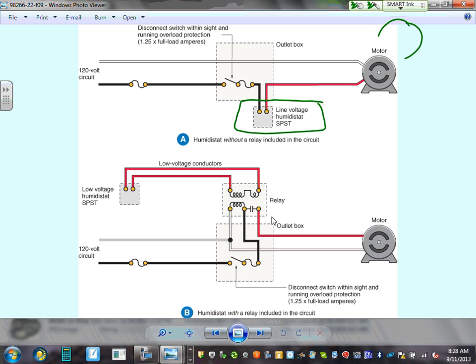You can buy a device like this, where you bring the hot in and the hot out, made to be a humidistat that controls that fan based on the humidity in the area. They call it line because can you guys see the voltage here is 120. So you go through the disconnect and overload, see that overload and disconnect here, and then the humidistat is tied to it. That's so-called line one. The load, the line humidistat, low voltage humidistat, right here.